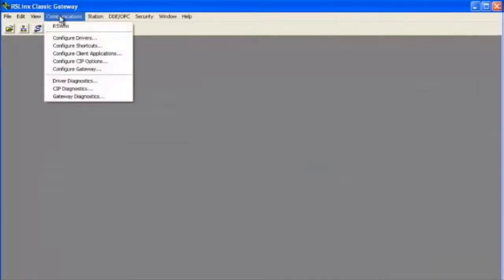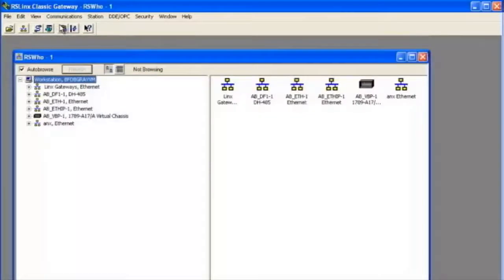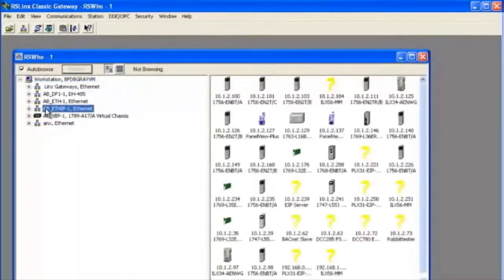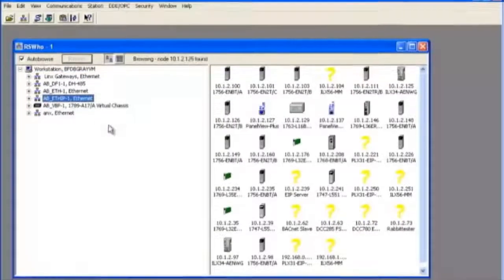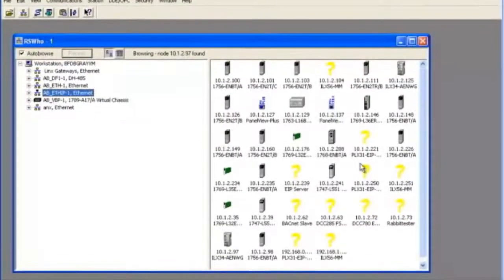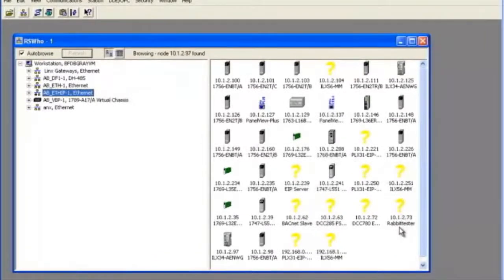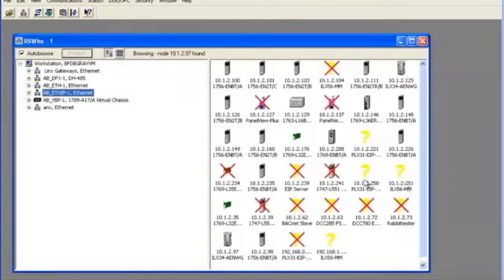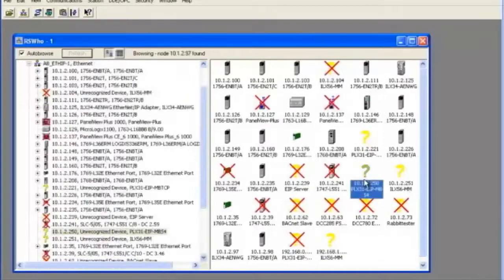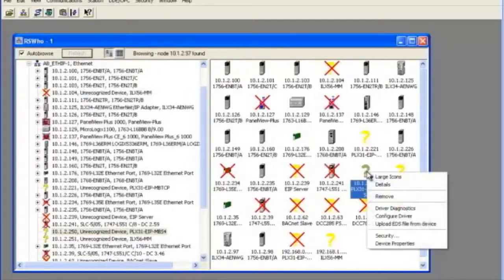Now we're going to bring in the EDS file using RSLinx Classic. So I open up RSLinx Classic and click connections, RS who, open up Ethernet IP and choose our device which is going to be 10.1.2.250.